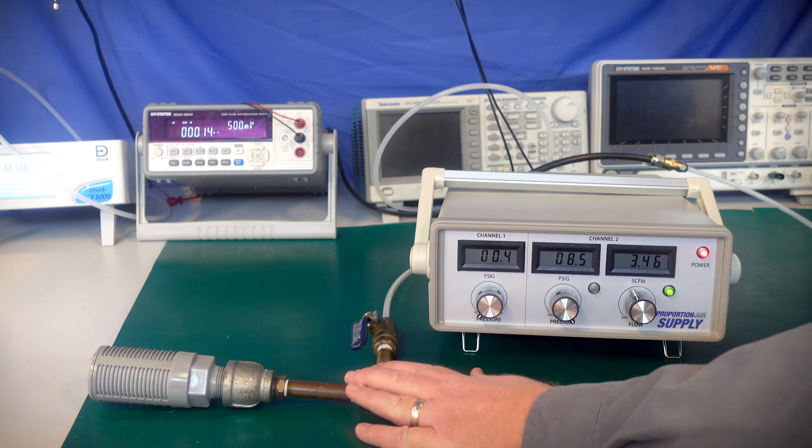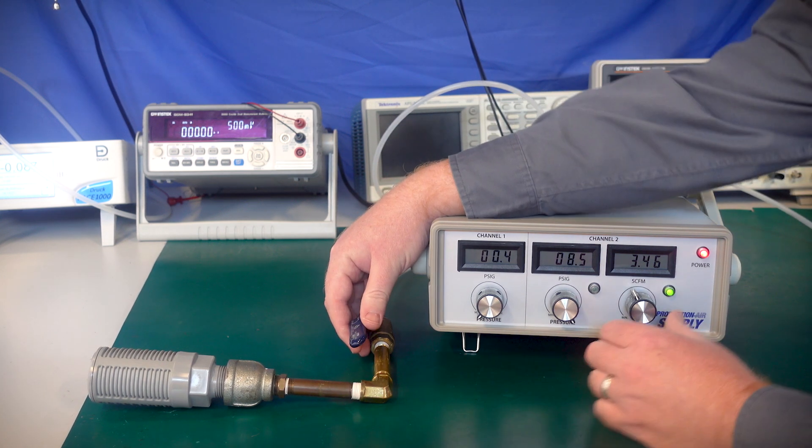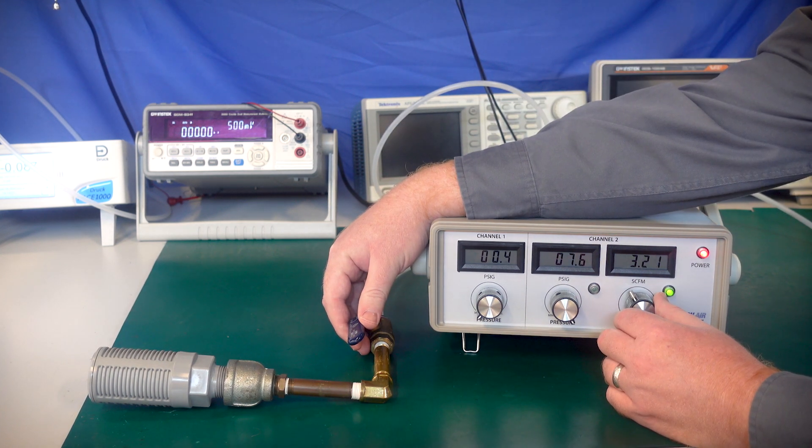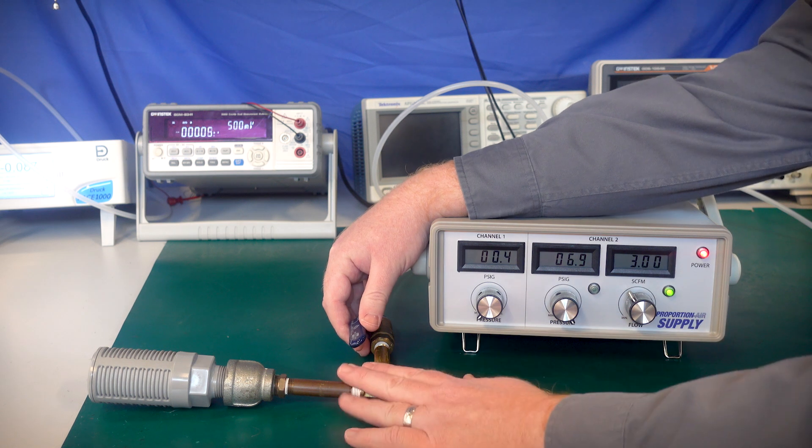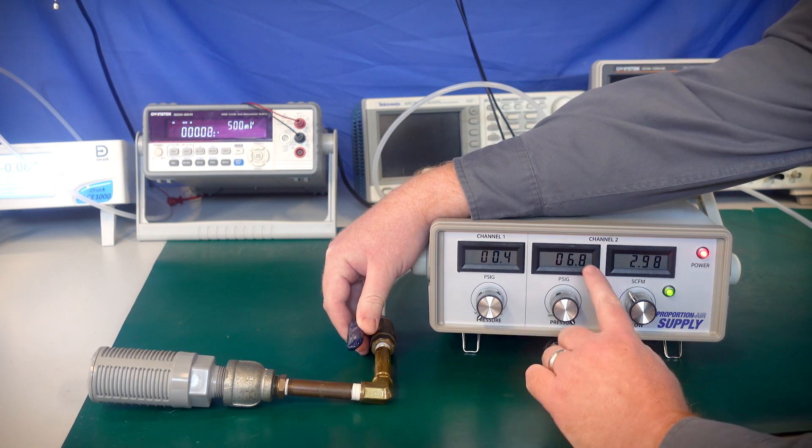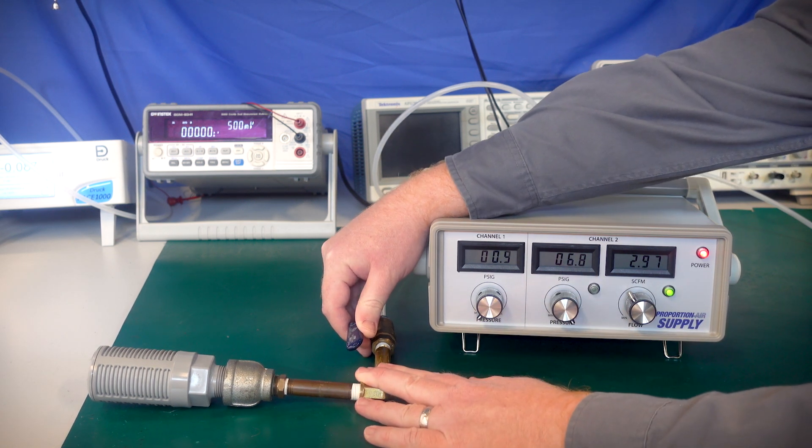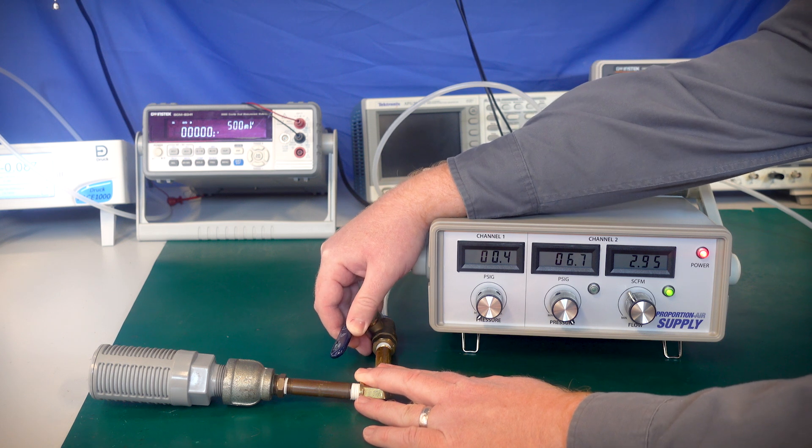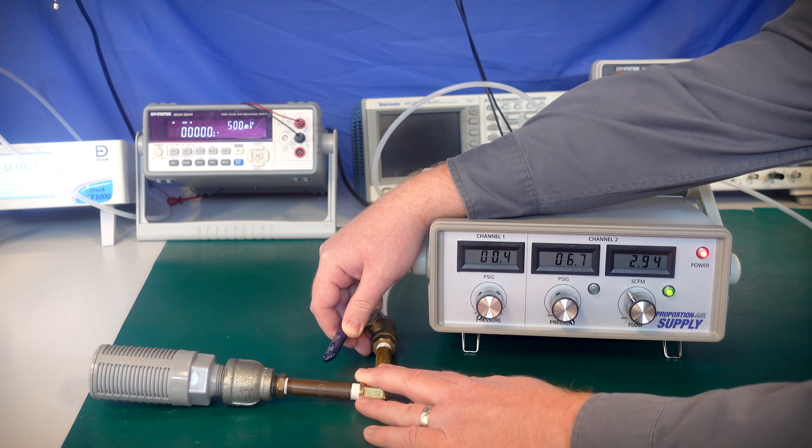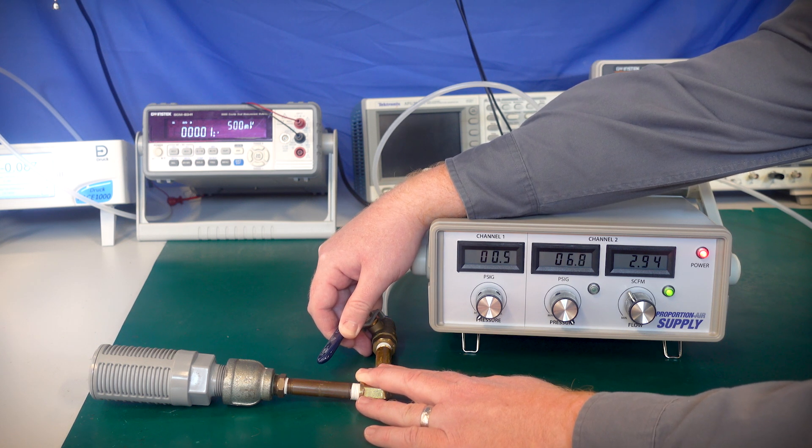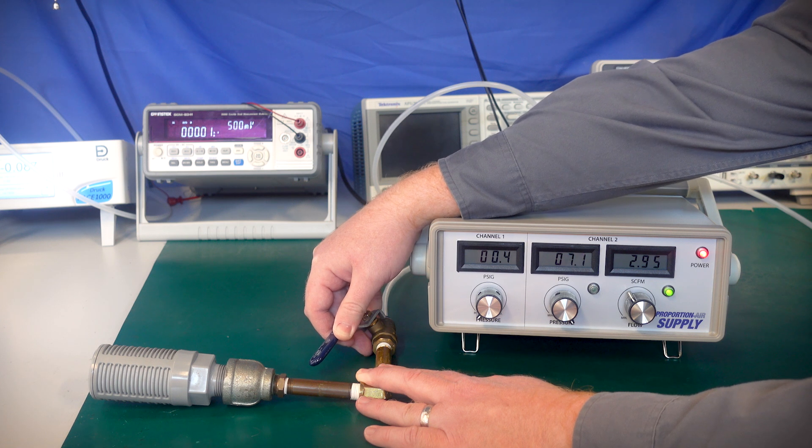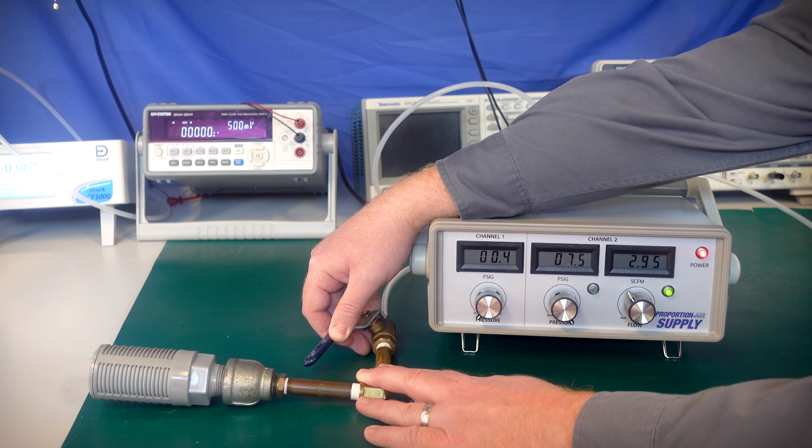Through this ball valve, if we set the flow to about 3 SCFM, we see it takes almost 7 psi. As we start to close this ball valve or put some kind of restriction, the pressure will begin to increase to maintain the flow rate.